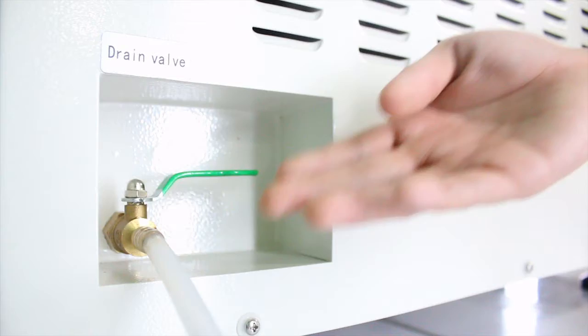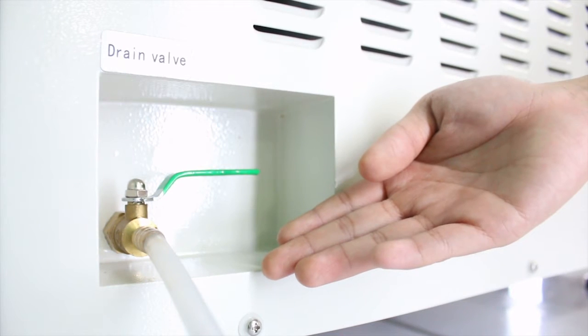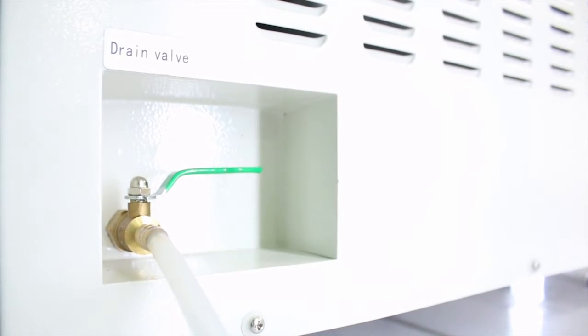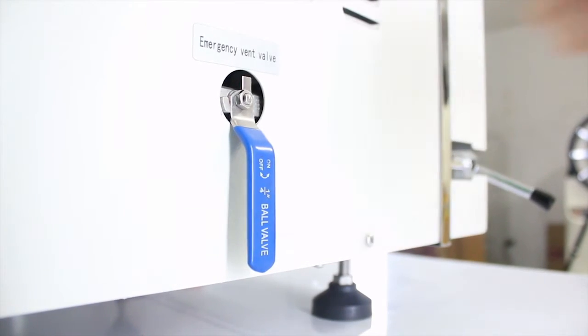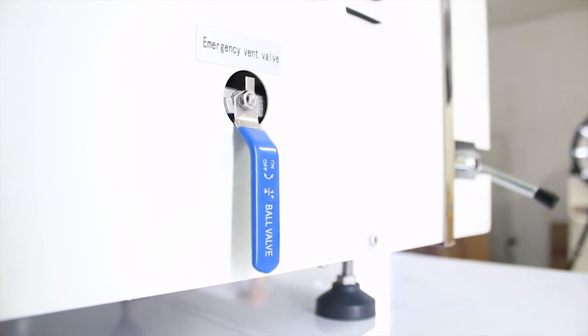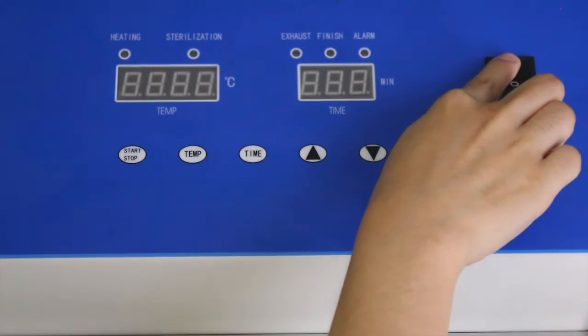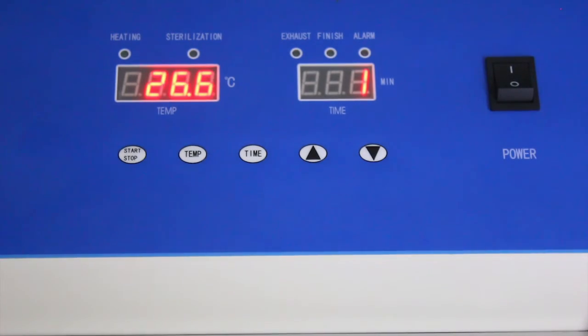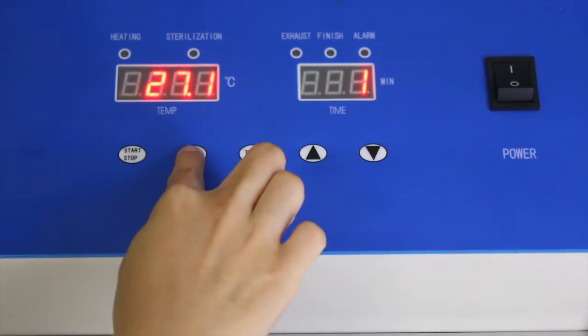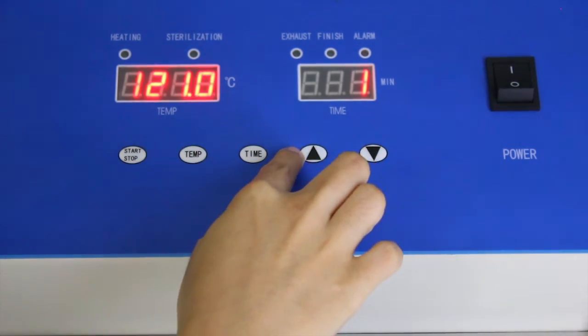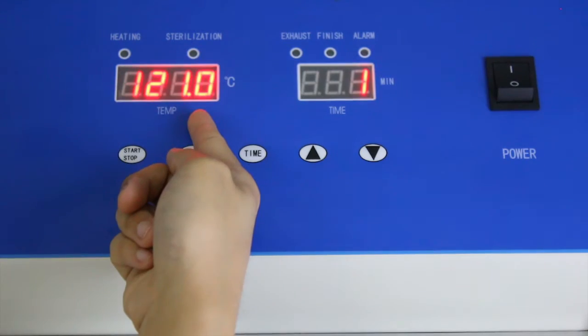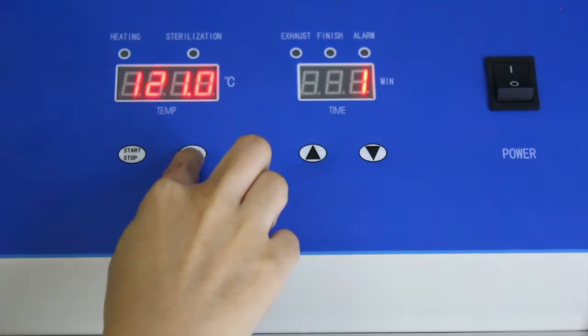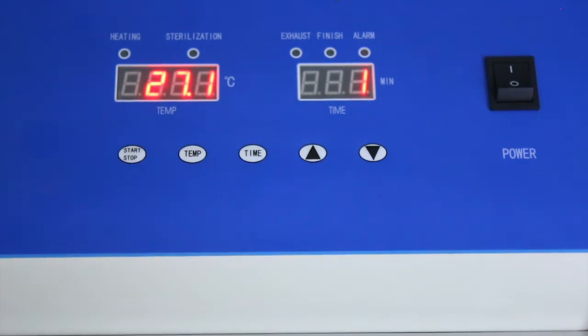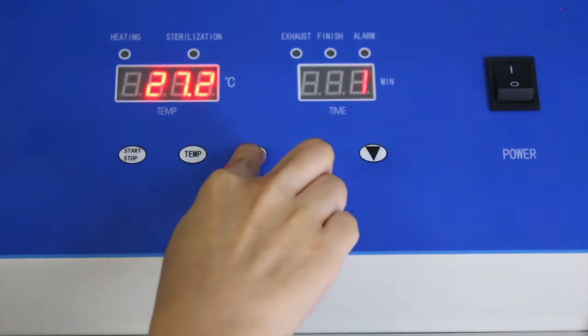Check to make sure that both the drain valve and the emergency vent valve on the left side of the autoclave are closed. Turn on the main power switch found on the control panel. Set the desired temperature. For sterilization, the factory setting is 121 degrees centigrade. You may go up to 126 degrees centigrade. Set the sterilization time to 20 minutes.